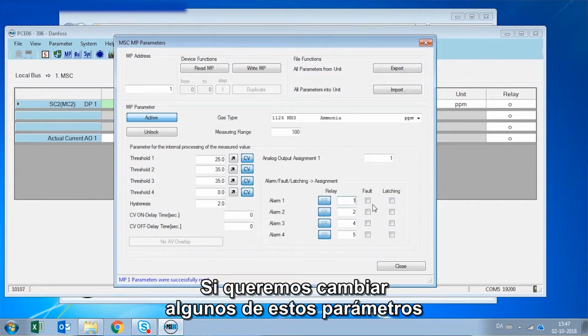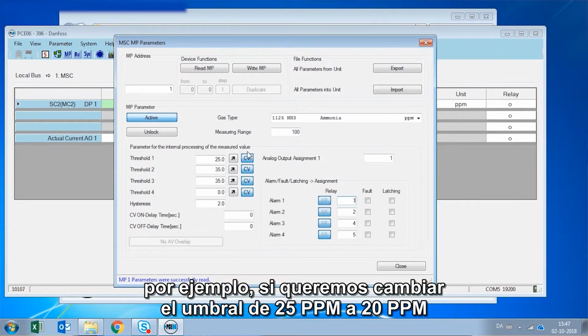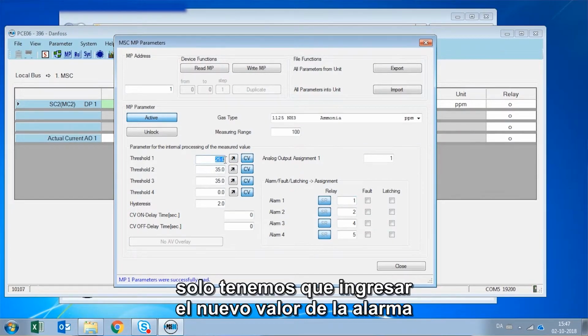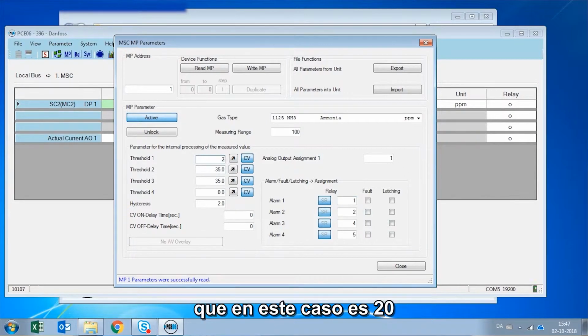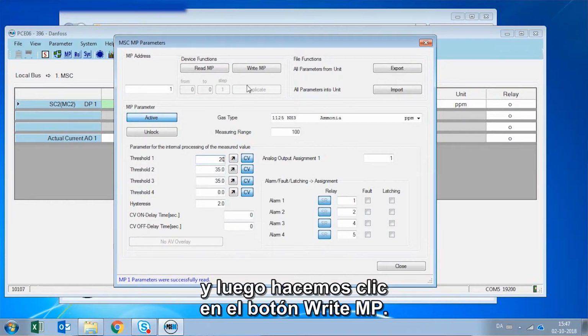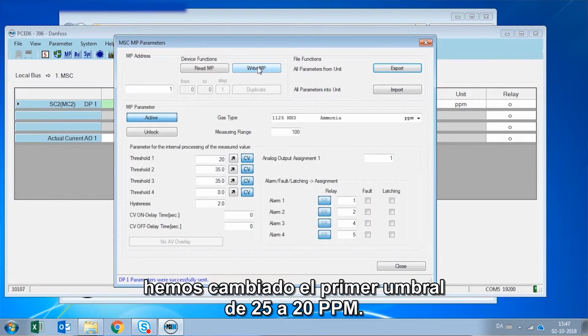If we want to make a change in some of these parameters, for example, if we want to change the threshold from 25 ppm to 20 ppm, all we have to do is enter the new value of the alarm, which in this case will be 20, and then click the button Write Measuring Point. By writing the measuring point, we have changed the first threshold from 25 to 20 ppm.